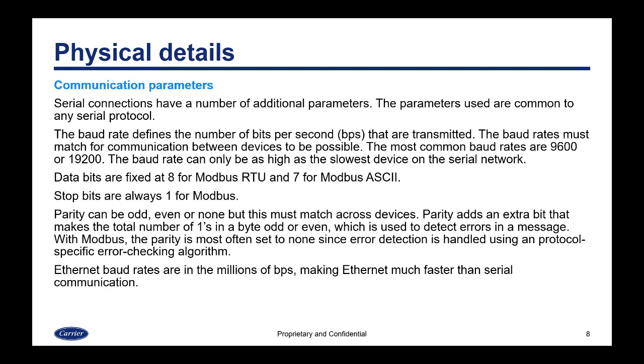Data bits are fixed at 8 for Modbus RTU and 7 for Modbus ASCII. Stop bits are always 1 for Modbus. Parity can be odd, even, or none, but must also match across devices. Parity adds an extra bit that makes the total number of ones in a byte stream odd or even, which is used to detect errors in a message. With Modbus, parity is most often set to none since error detection is handled using a protocol-specific error checking algorithm.